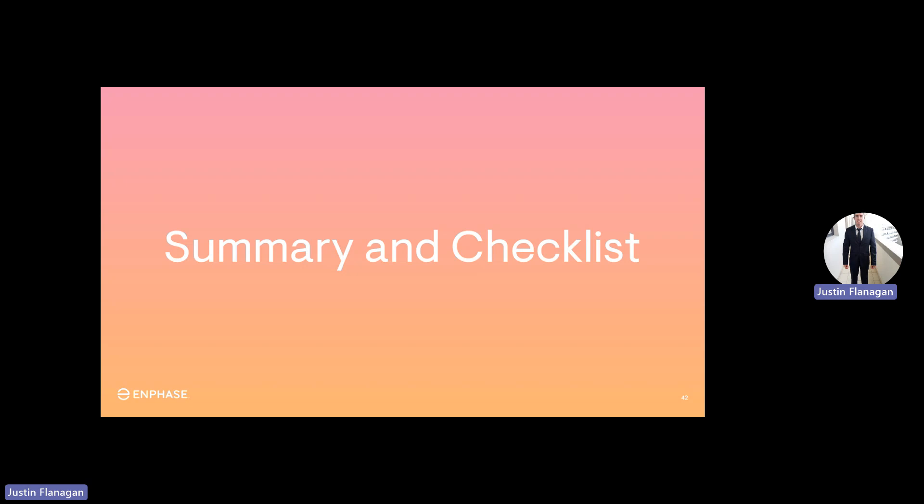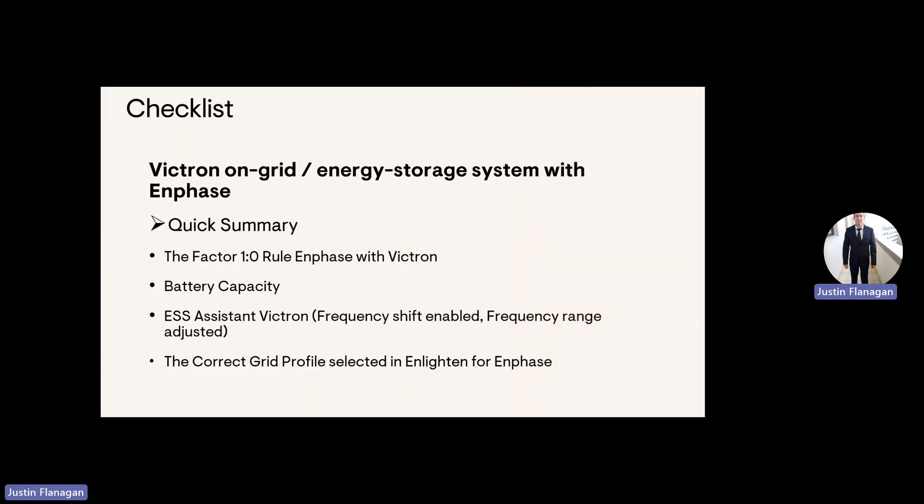We'll have a look quickly at the summary and checklist with Victron. The quick summary is the number one rule factor. Remember the rule where if the Victron is 8 kVA, you're only allowed 8 kilowatts of power from the PV on the backup side. The battery capacity, the ESS Assistant has been selected for the frequency range, and the correct grid profile has been selected for the Enphase on the Commissioning Toolkit.